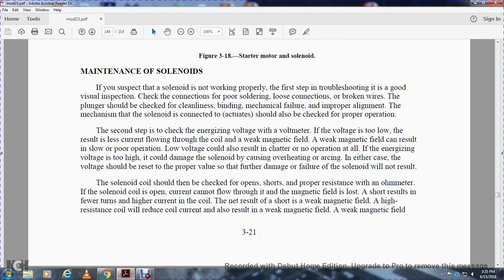The second step is to check the energizing voltage with a voltmeter. If the voltage is too low, the result is less current flowing through the coil and a weak magnetic field. A weak magnetic field can result in slow, poor operation. Low voltage can result in chatter and no operation at all. If the energizing voltage is too high, it could damage the solenoid, causing overheating and arcing. In either case, the voltage should be reset to the proper value, so that further damage and failure of the solenoid will not result.